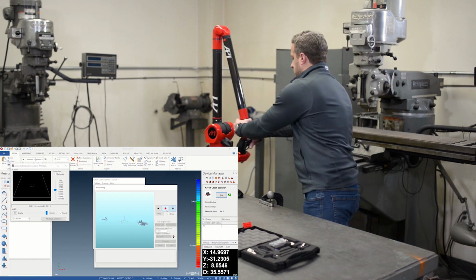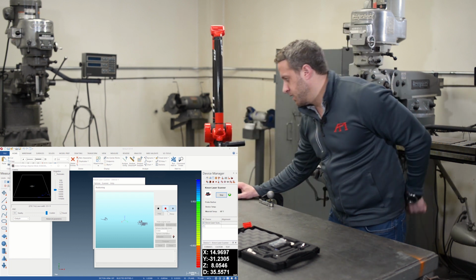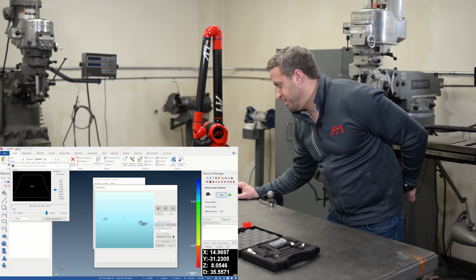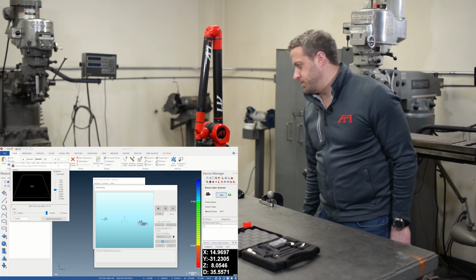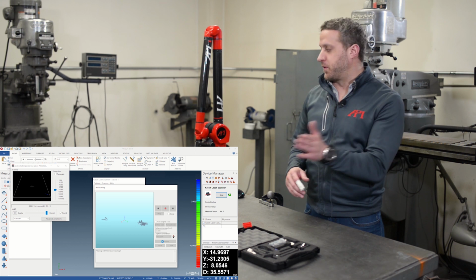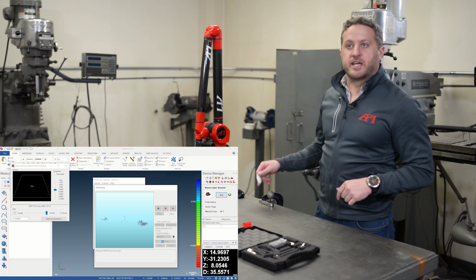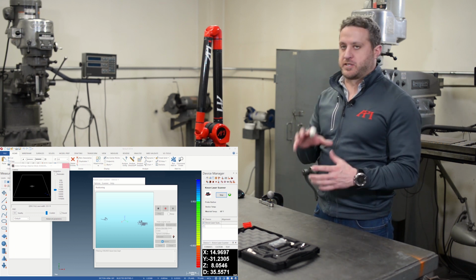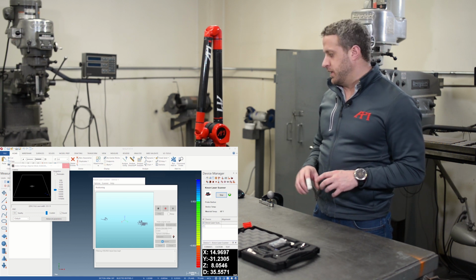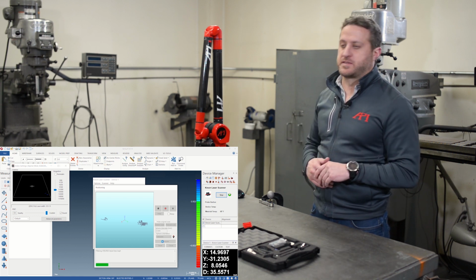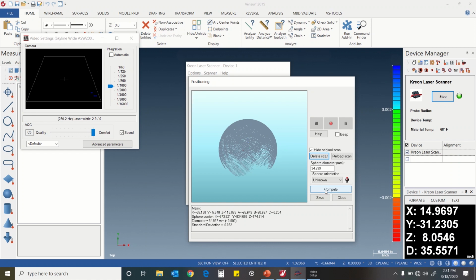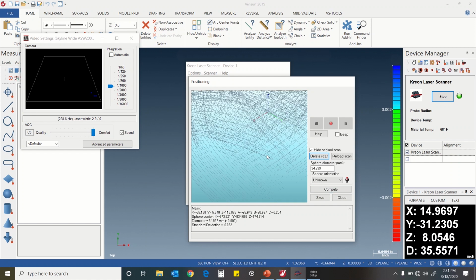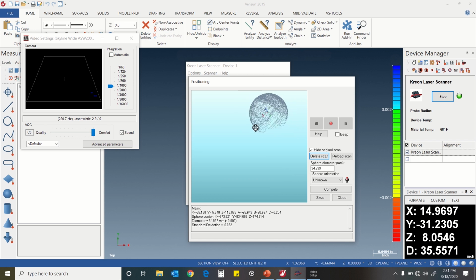When we're done, we'll stow the arm, we'll press stop, and we'll hit compute. So right now it's filtering out a lot of the flyer data, table, clamp, and it's trying to pull out that sphere, and it's going to calculate it and give us our results of the calibration. So after it computes the sphere, you can see that it pulled out quite a bit of the sphere. We can zoom in, you can see what kind of data it collected.